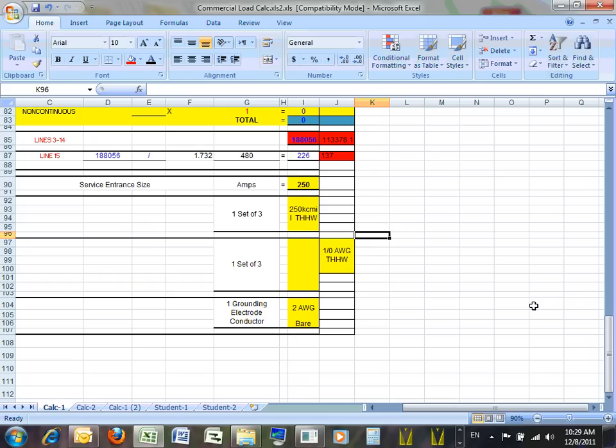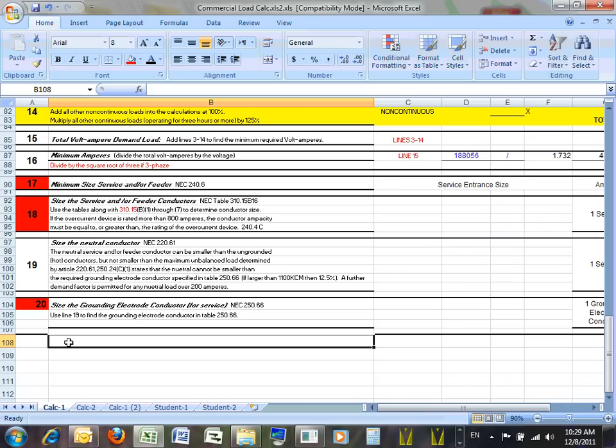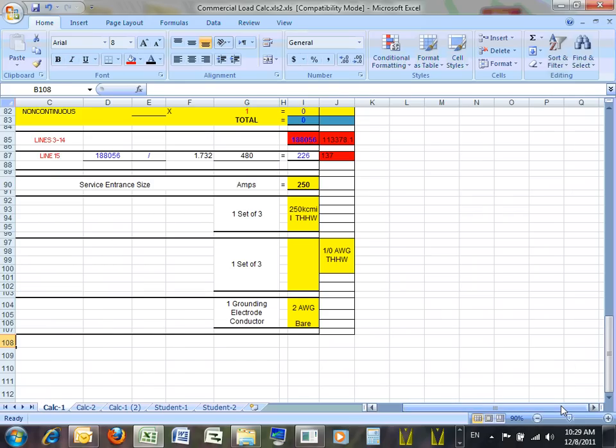So now, you have a PVC conduit. We didn't size the PVC conduit, but right here, guys, you're going to size the PVC conduit for me. I have a conduit that has the following conductors: three conductors, 250 kcmil THHW, and one conductor, 1/0 THHW, and you're going to size a PVC schedule 80, commercial schedule 80, underground, and size the conduit. Anybody does not know how to size a conduit? If you need four conductors, different sizes, right? Chapter 9, Tables 5 and 4. Any question about this?